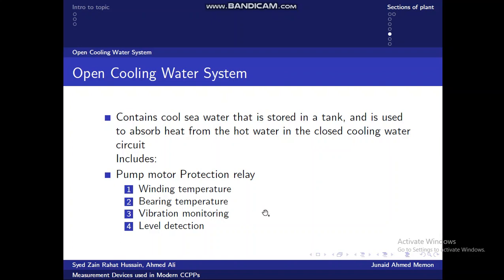So this includes the pump. There are two vertical pumps that are present. One is functional, one is on standby. The pumps have a flow rate of 2,600 meter cube per hour and 4.5 bar discharge pressure. So the pump motor protection relay is constantly measuring the winding temperature of the motor, bearing temperature, vibration monitoring, and level detection of the tank.